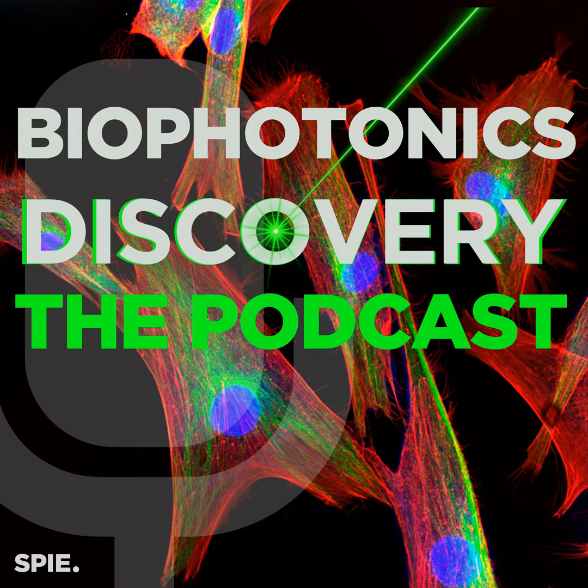But we learned that the LEDs weren't bright enough. And so we next created this Gen 3 device where we actually are pulsing the LEDs. So we're pulsing them at high frequency and they're really bright pulses, but we are syncing those pulses with the frame clock of the camera so that it always appears on to the end user, but we don't generate too much heat because in reality, the LEDs are actually off the majority of the time. And this is just an exploded view of the Gen 3 laparoscope. And we have all these O-rings that help waterproof the device.